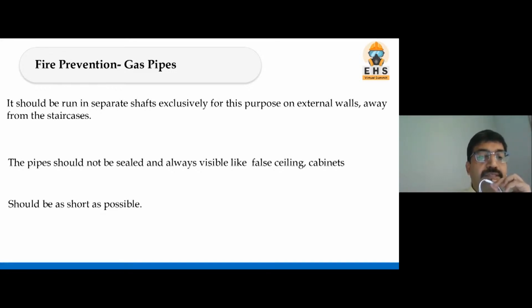The pipe should not be sealed and should always be visible. Just imagine whoever has natural gas piping at their residence - what we do is try to hide that gas pipeline, but it is not safe as per NBC and also logically. It should be clearly visible so that if something happens, we can take action. But we normally try to hide it inside false ceilings or cabinets and so on.